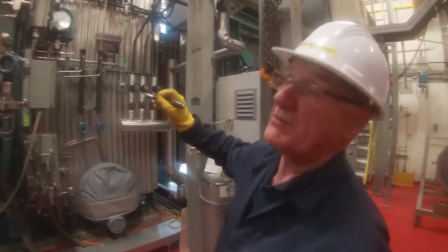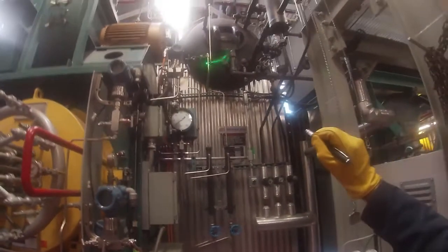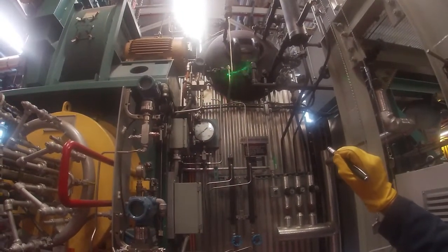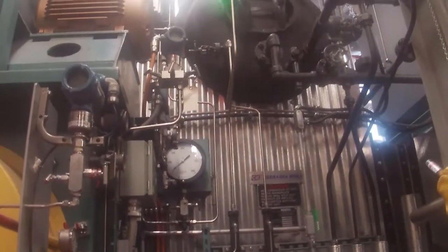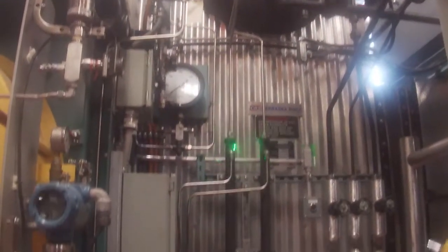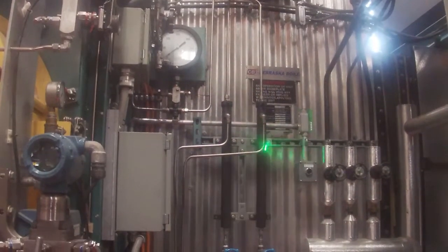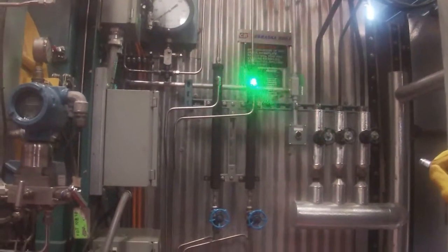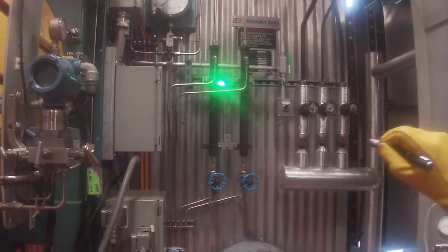Okay, we're back down on the main floor, and you can see the drum taps. That's the high pressure tap, the high level tap on the bottom of the drum, and the compensating or low pressure tap on the top of the drum. They come down through settling chambers to settle the sludge out, and then come off their taps at that point and that point, coming into the drum level transmitter.